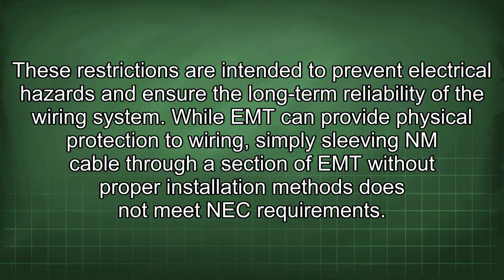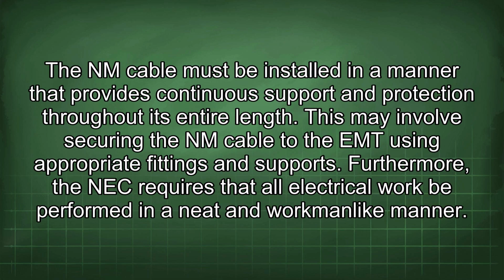While EMT can provide physical protection to wiring, simply sleeving NM cable through a section of EMT without proper installation methods does not meet NEC requirements. The NM cable must be installed in a manner that provides continuous support and protection throughout its entire length. This may involve securing the NM cable to the EMT using appropriate fittings and supports.